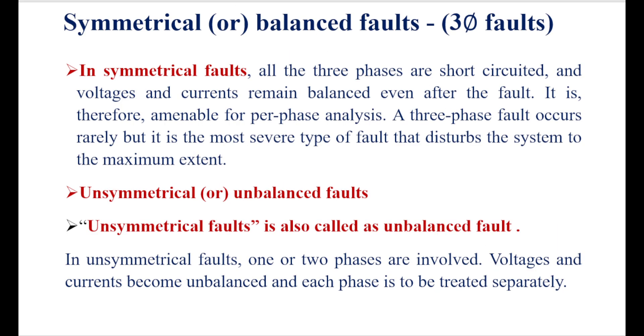A symmetrical or balanced fault is a three-phase fault in which all three phases are short circuited. Voltages and currents remain balanced — voltage decreases and current increases, but the system remains in balanced condition even after the fault. This makes it amenable for per-phase analysis: calculating values for one phase gives the answer for the other two phases. Although a three-phase fault occurs rarely, it is the most severe type and disturbs the system to a maximum extent.